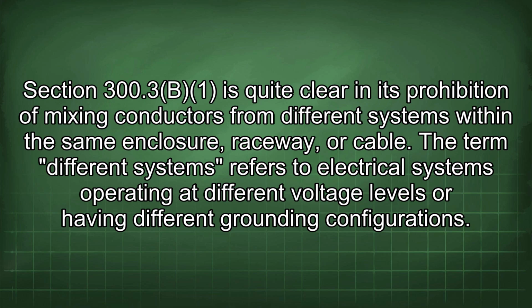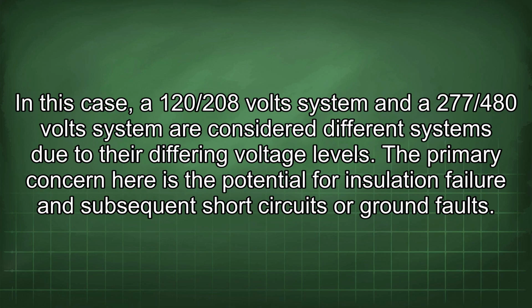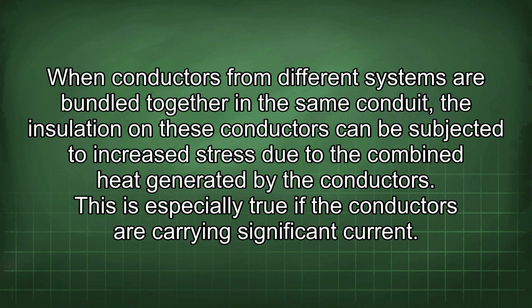The term different systems refers to electrical systems operating at different voltage levels or having different grounding configurations. In this case, a 120/208 volt system and a 277/480 volt system are considered different systems due to their differing voltage levels. The primary concern here is the potential for insulation failure and subsequent short circuits or ground faults. When conductors from different systems are bundled together in the same conduit, the insulation on these conductors can be subjected to increased stress due to the combined heat generated by the conductors. This is especially true if the conductors are carrying significant current.